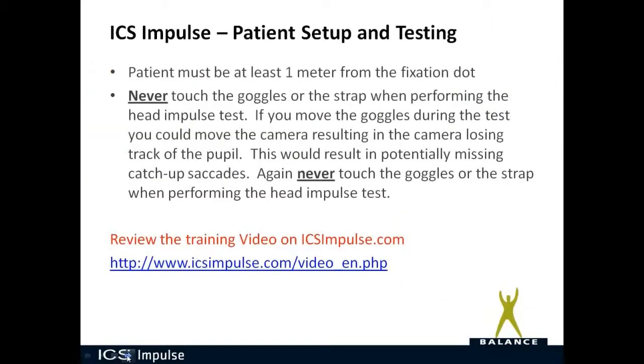Now let's talk about patient setup and testing. The patient must be at least one meter from the fixation dot. Having a very close target activates convergence — the eyes have to cross in order to look at the dot. Activation of the convergence system may interfere with the vestibular ocular reflex. In addition, a close target adds a linear component where the eyes move sideways relative to the dot, an effect that becomes smaller with increasing distance. That's why it is recommended the patient be at least one meter away from the fixation dot.